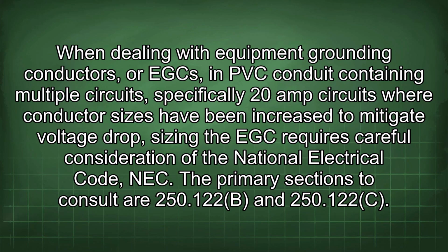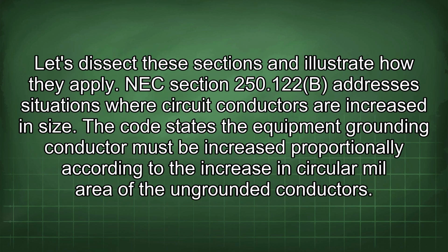When dealing with equipment grounding conductors, or EGCs, in PVC conduit containing multiple circuits, specifically 20 amp circuits where conductor sizes have been increased to mitigate voltage drop, sizing the EGC requires careful consideration of the National Electrical Code (NEC). The primary sections to consult are 250.122(B) and 250.122(C). Let's dissect these sections and illustrate how they apply.